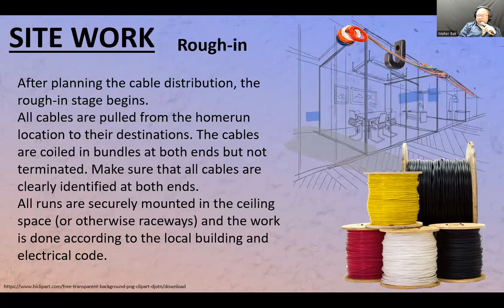The problem with that is, God forbid there's a fire—the fire crews have to do whatever is needed to get to the point where the fire is, or to make sure things are safe. Part of that is they sometimes bring the ceiling structure down, the suspended ceiling. They have these hooks on a stick, and they grab things hanging from the ceiling and bring them down to make things safe. So if more things are tied to that structure, the more difficult the job becomes and the more unpredictable the outcome.